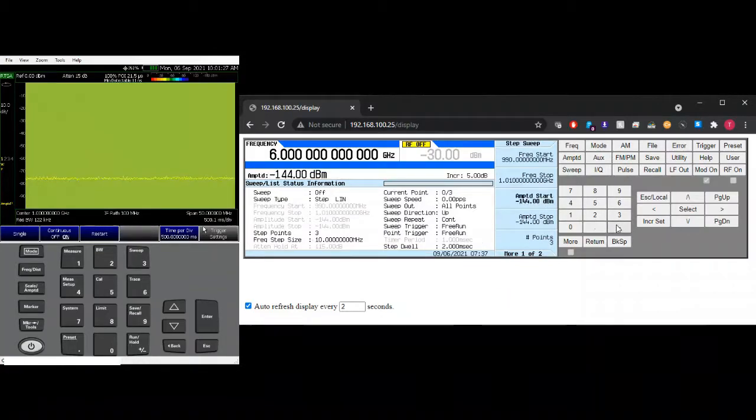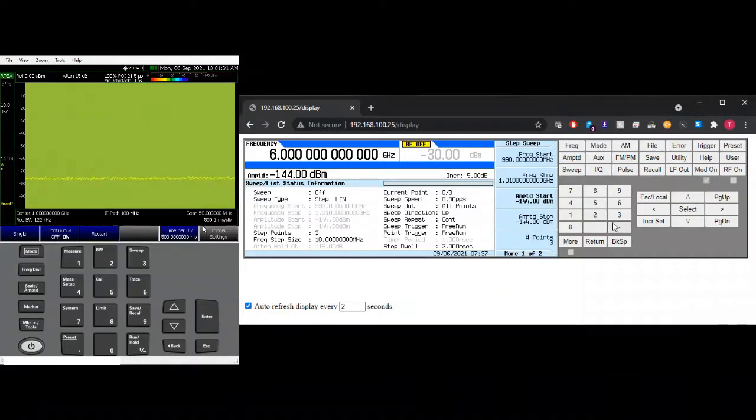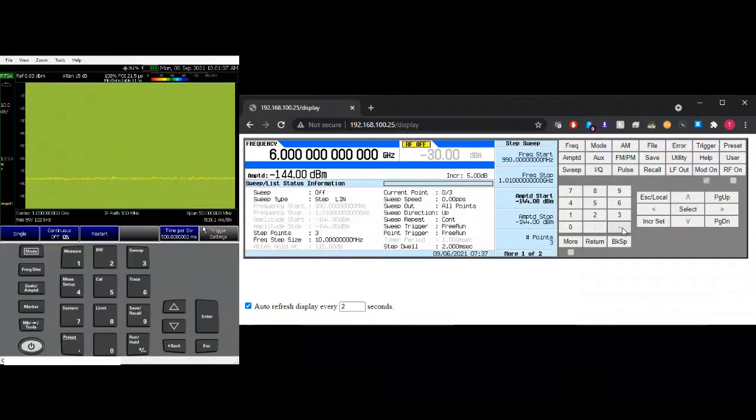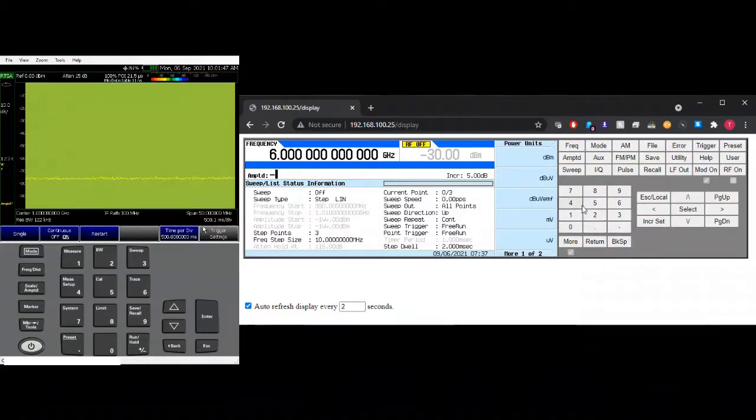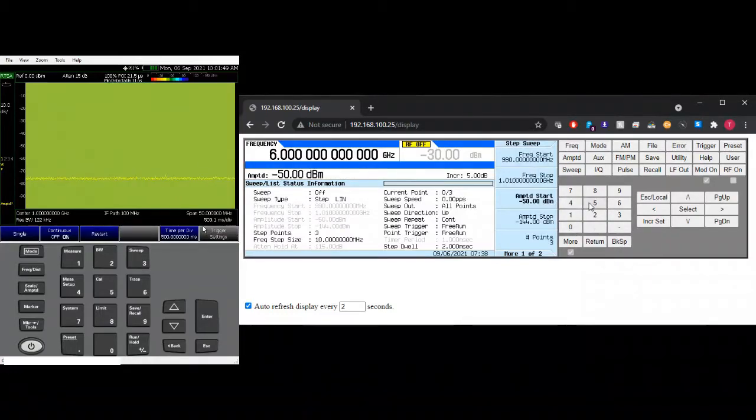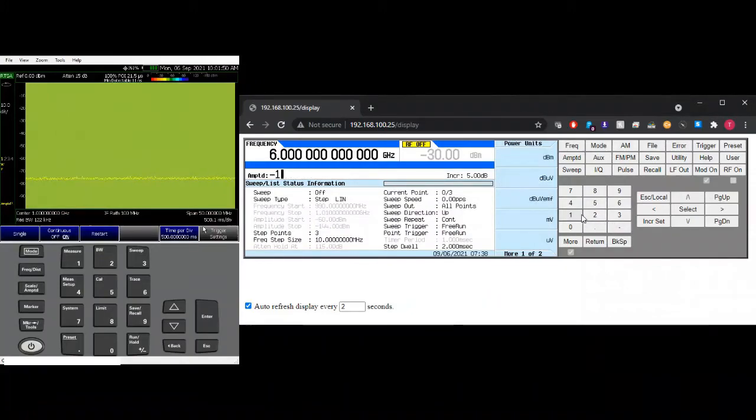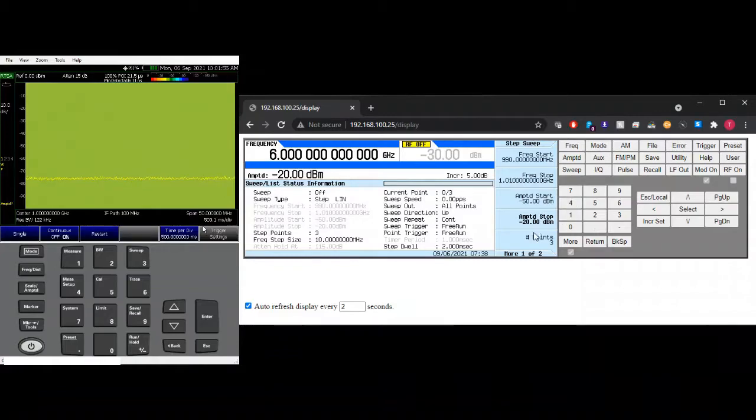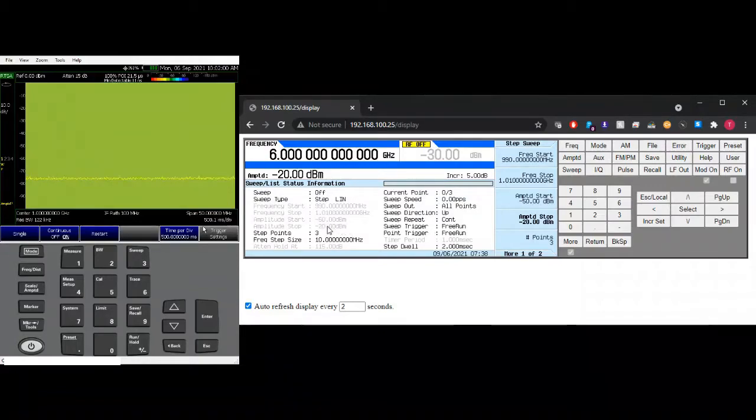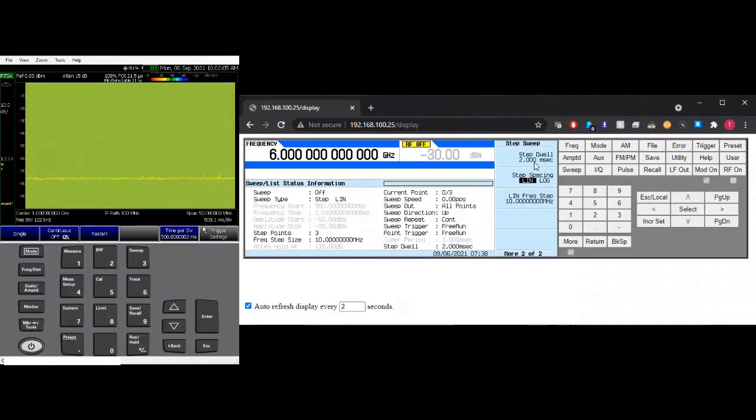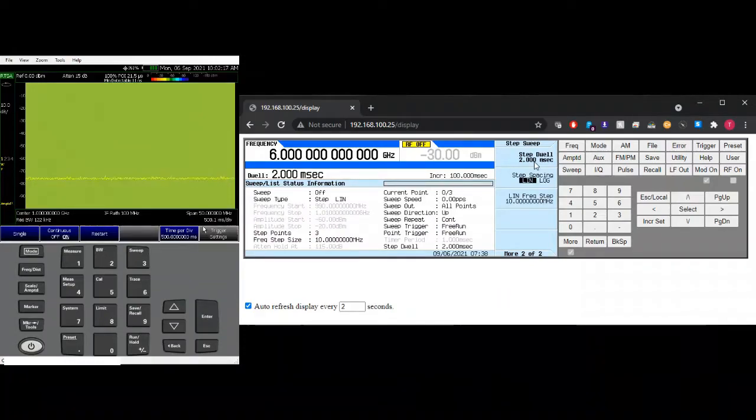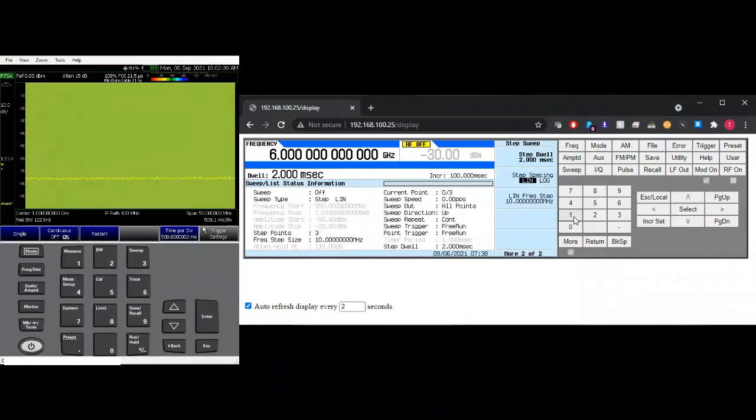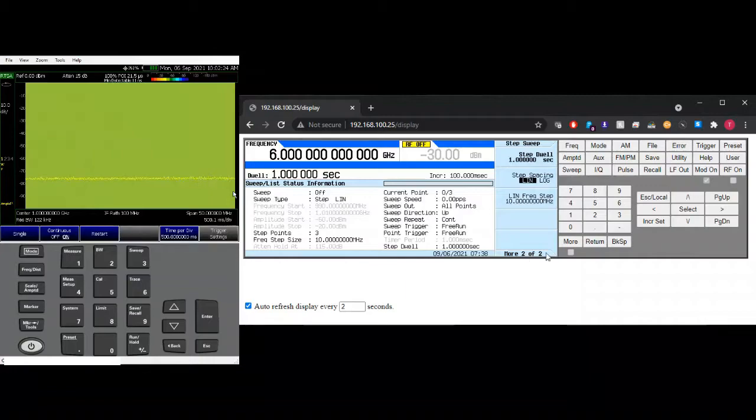And amplitude, if you want it to be flat or you want it to go different steps, you can also set it here. So we're going to show you what is the effect from doing that. So let's say we set it from minus 50 to minus 20. So each step would be, it's not saying here. So this is a summary of your setting. So dwell time, every step you can set to delay and stop at the same step for any amount of time that you want. For this exercise we set it to 1 second so that we can see over here clearly.